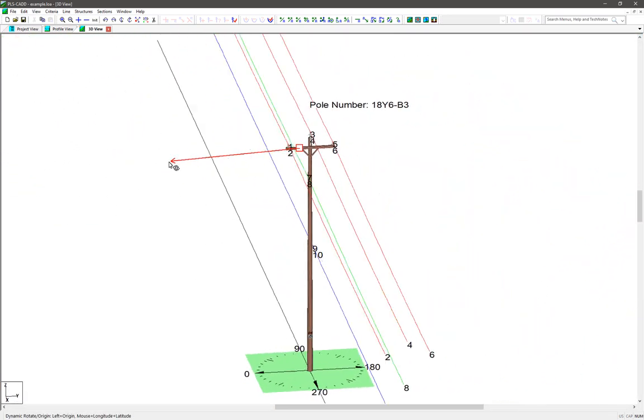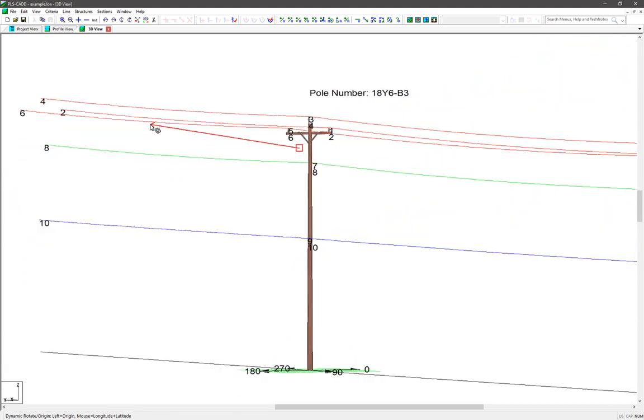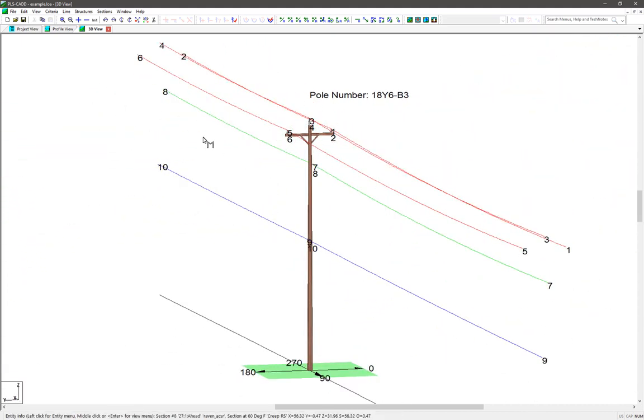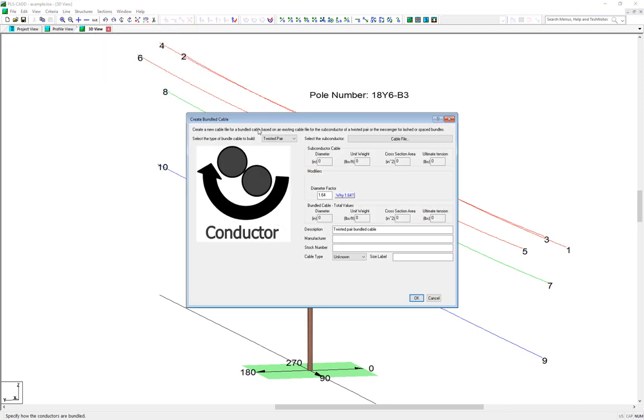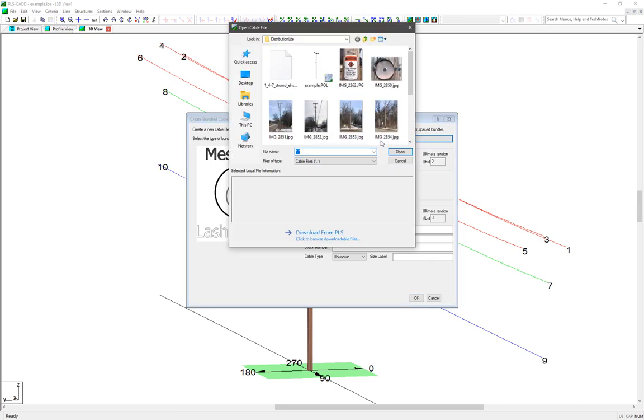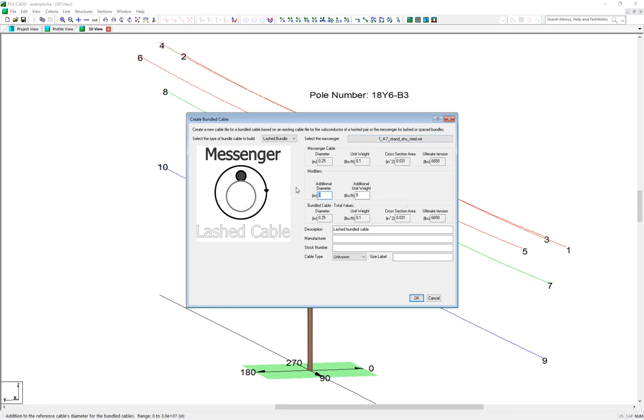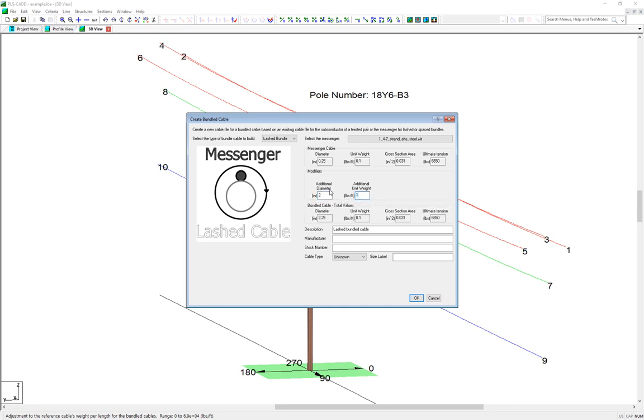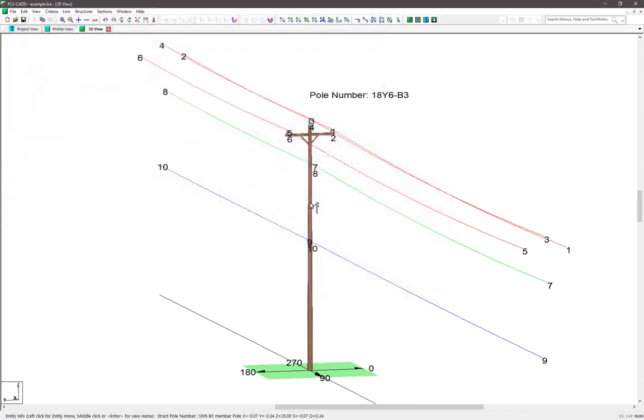All we need now is to make the communication cable. To do that, we navigate to Sections, Create Bundled Cable File, and we change the bundle type to be a lashed cable. Then we select the messenger wire here, which is the 1/4 inch steel wire that carries all the tension. Then in the modifier section here, we input the additional diameter, which we said was going to be 2 inches, and the additional weight of that cable, which we said was 1.4 pounds per foot. Then we add some additional information and notes about the bundled cable file we're making, and click the OK button, and give it a file name.